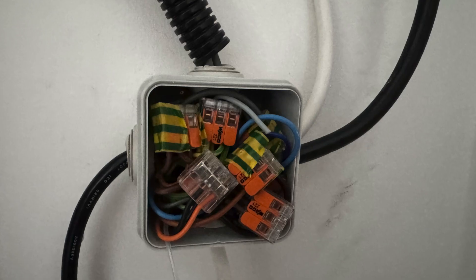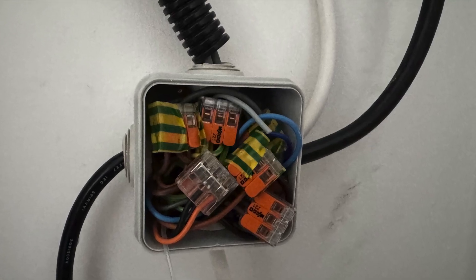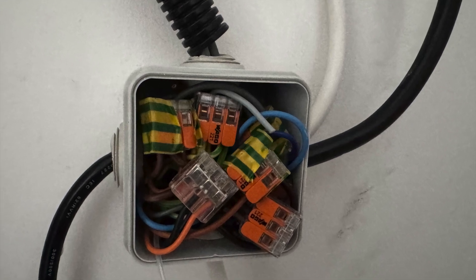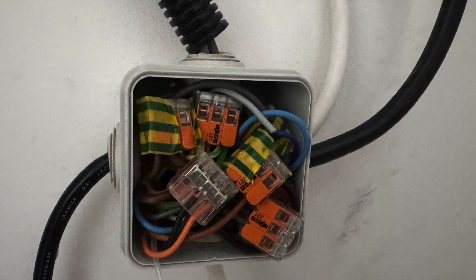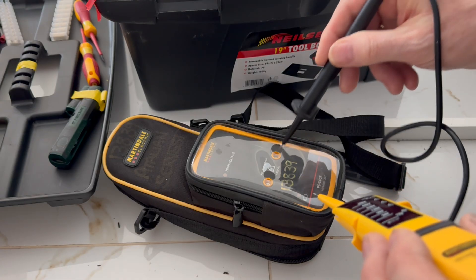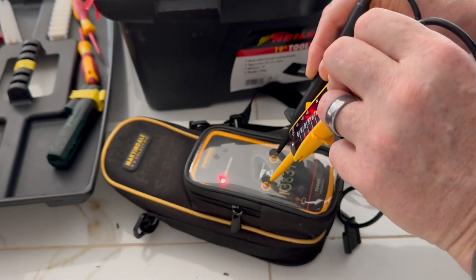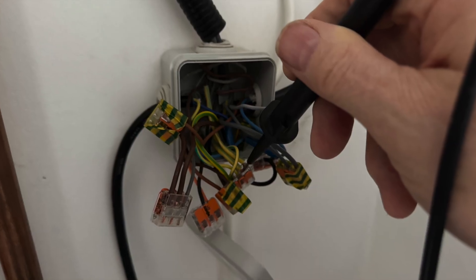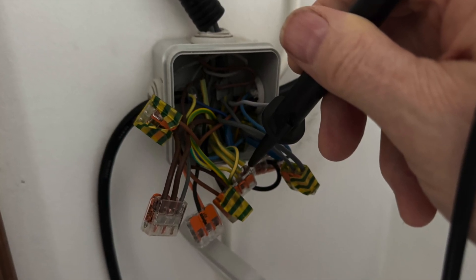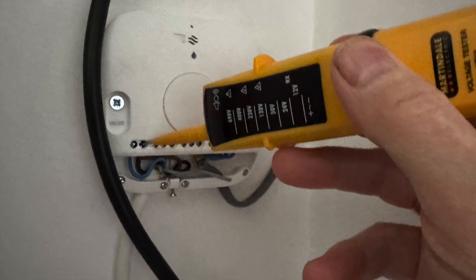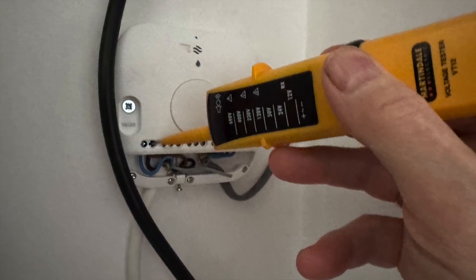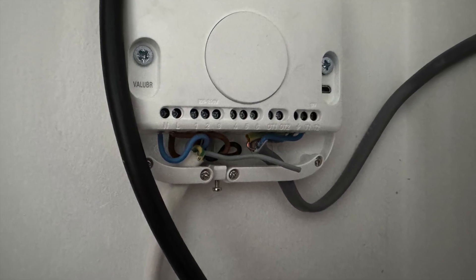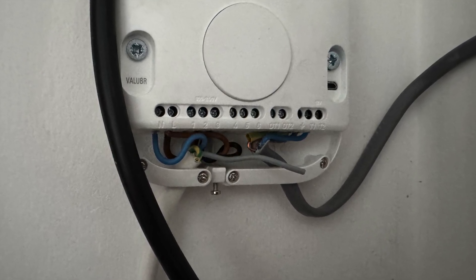Now I need to carry out my safe isolation procedure. I need to carefully remove this tangle of wires out of this incredibly small box. First thing I'm going to prove my two pole tester's working with my proven unit. I'm testing from the earth wire to all the live wires that go to the stat. Now I know that the power has been correctly isolated.